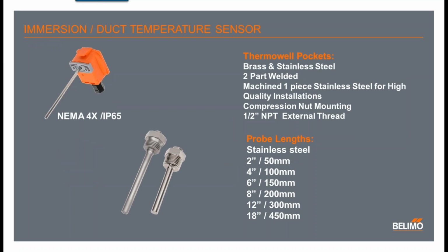Our immersion sensors, the same as our duct sensors as we mentioned, come from 2-inch to 18-inch. We also have thermal pockets which are available in brass and stainless steel, 2-part welded, or we can offer one machined out of one-piece stainless steel for high quality installations. All of our thermowells are equipped with a compression nut mounting feature versus the industry standard set screw grub screw type, all complete with 1/2-inch MPT external threads.